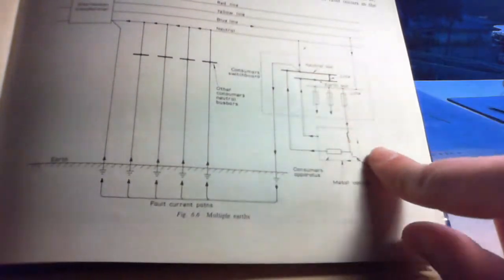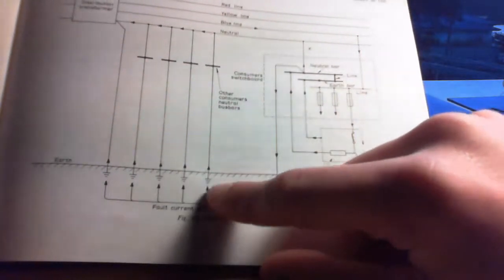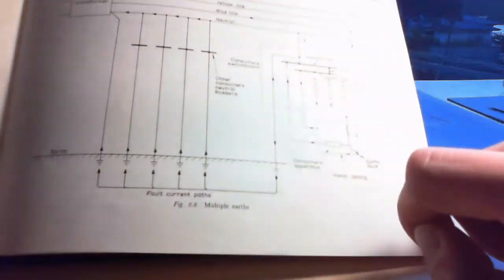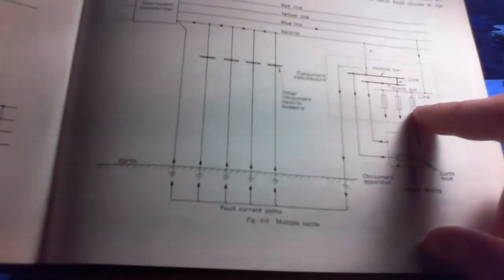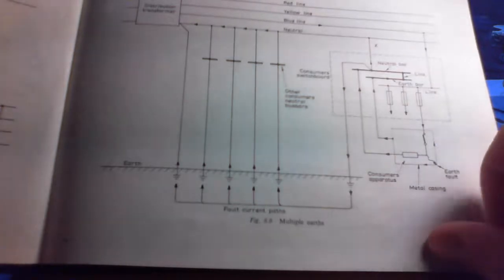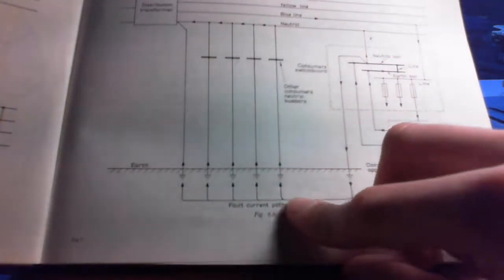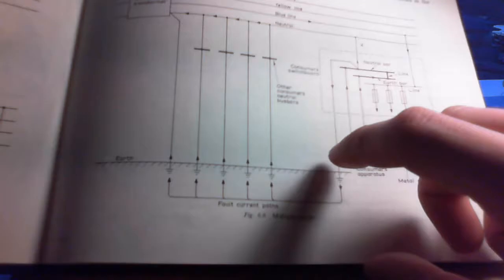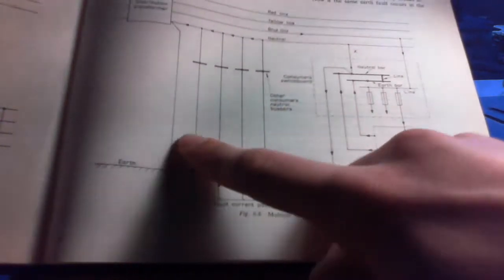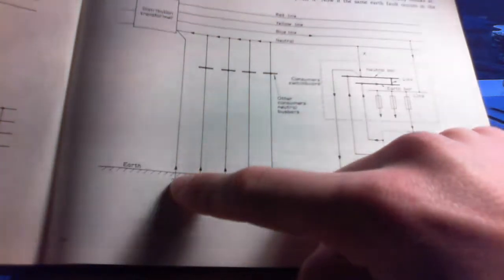So just say if this happened at my place, my neighbour would be receiving some voltage going into the neutral bus bars and back into the neutral line, going back to the distribution transformer. And obviously by that time, in seconds, that fuse would most likely have blown. But you see, all the electricity goes through my earth, through the house, into other people's, and also the distribution transformer has its own earthing stake, and it goes into there as well.